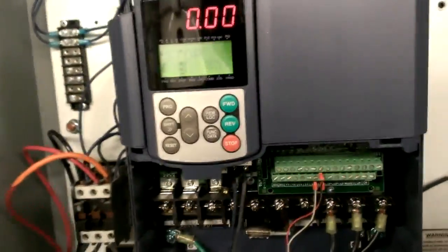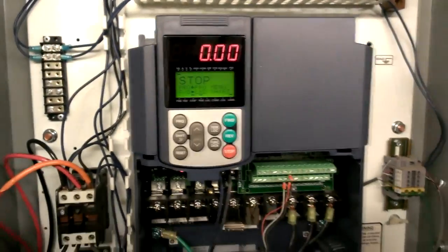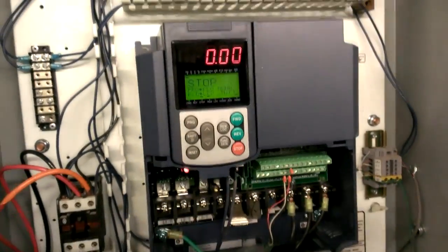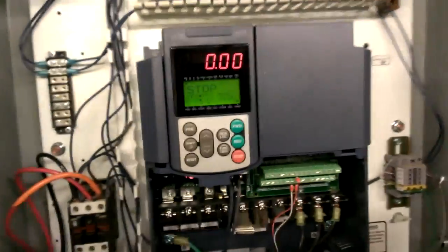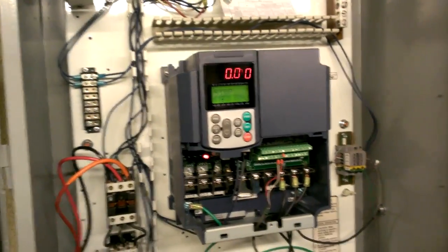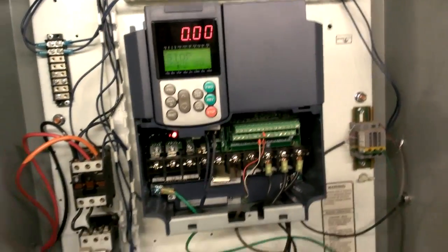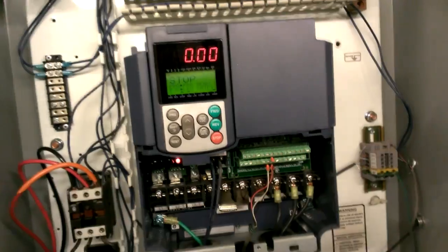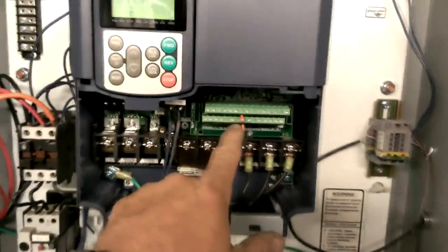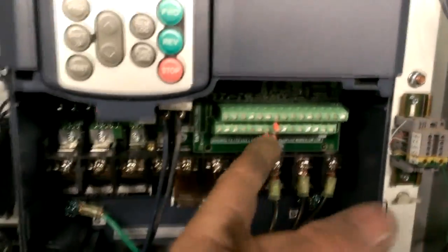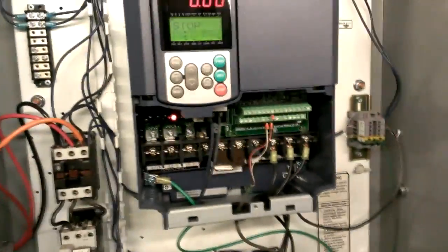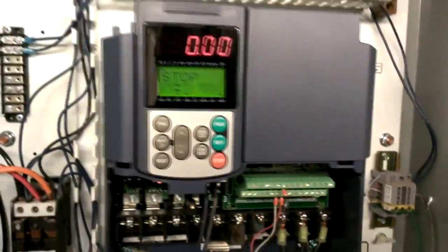That way, it's gonna maintain a certain pressure. And then, the higher the input, the more it's gonna slow down the motor. If I just leave it regular, then based on the input, it's how fast it wants to run the motor. So, it'll see the max signal. It'll just want to go as fast as it can. So, that's not the way you gotta run it. So, I need to set it up for inverse. And I need to make my own control.